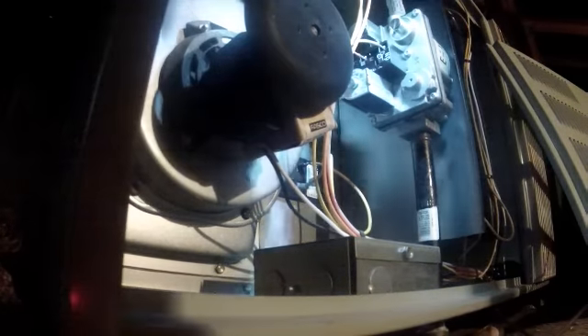And since we're here and we have about a 20-year-old system, I'm gonna go ahead and just double check this heat exchanger and make sure everything is good here. So I'm just gonna do a quick visual check. One of the most common places that the heat exchangers crack is right on the eyelets, just inside.